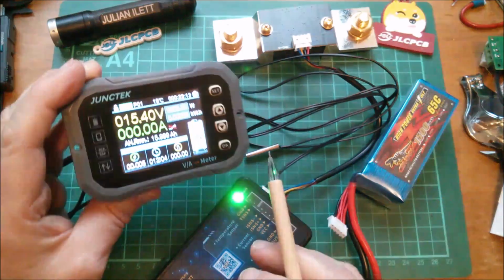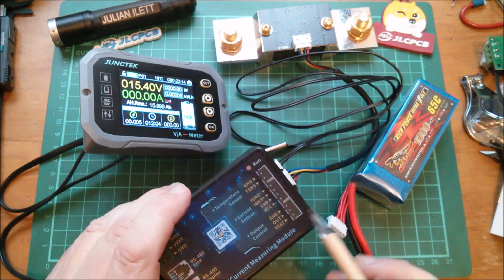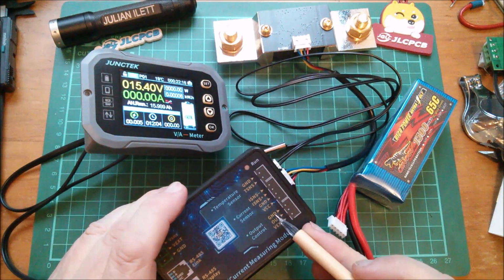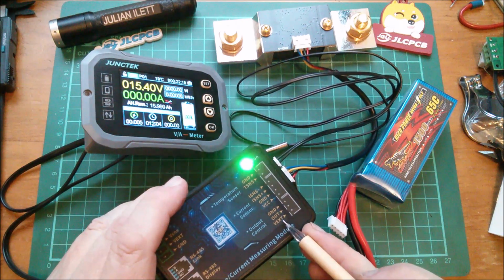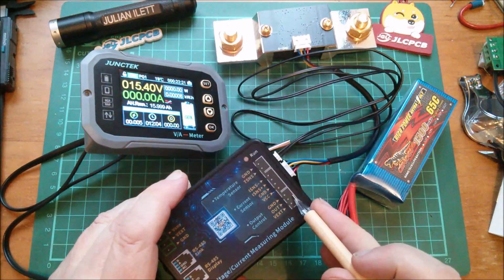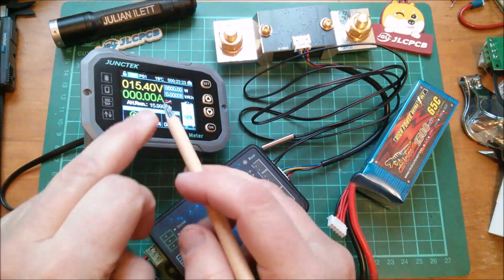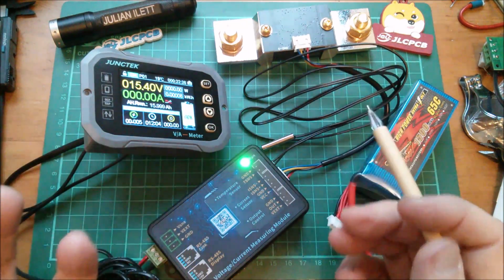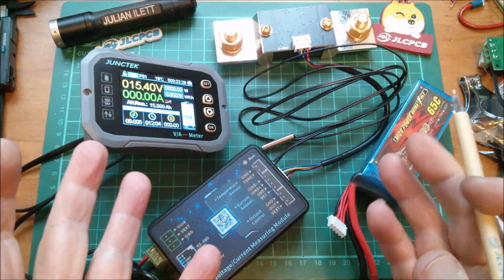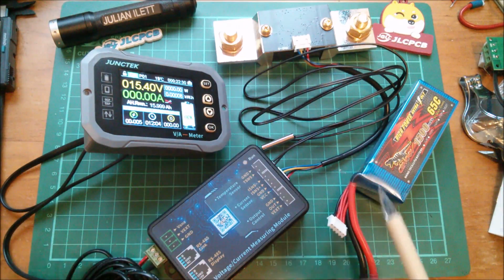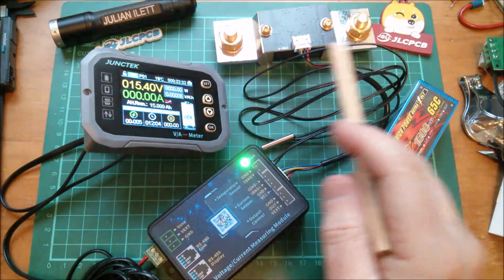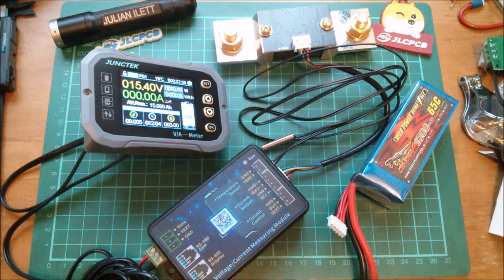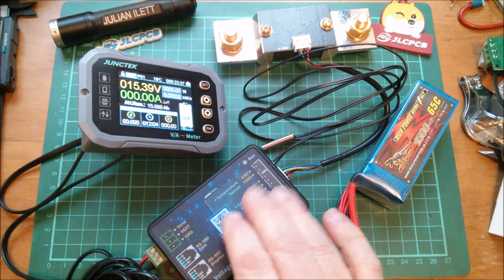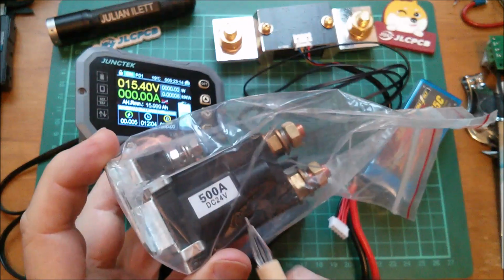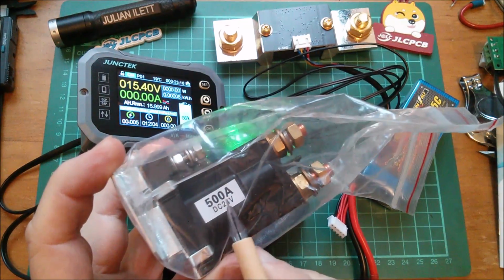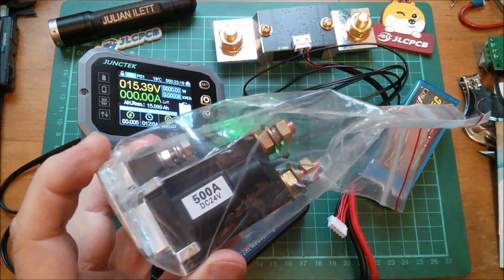Now there is a relay output on this box here, output control. We've got a ground, an out, and a V external. So this is where you hook up your relay, and then if any of the protections needs to disconnect the circuit, it will do it via your external relay. There's no relay built in, and that makes perfect sense because you might be trying to switch 400 amps and they're not going to put a 400 amp relay in this little box. However, sneak peek, 500 amps, 24 volts.